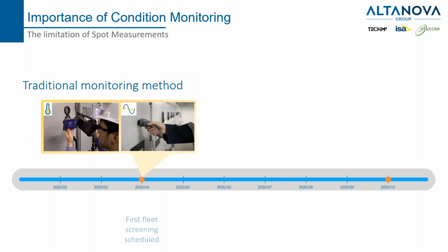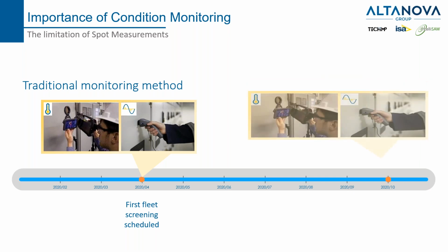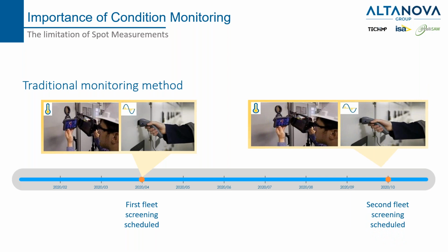Let's now talk about the traditional monitoring method. The traditional monitoring method actually relies on a few spot measurements in a year. That means basically it could be twice per year or even once per year. That is the history of the maintenance plan from the utility or from the private producer of energy. But of course, having the first spot measurement in the first half of the year and the second spot measurement, as per maintenance plan, in the second part of the year is not covering what could happen in between. And everything that can happen in between can also bring a failure.